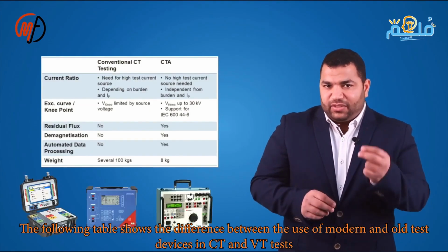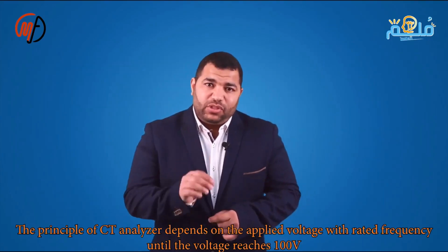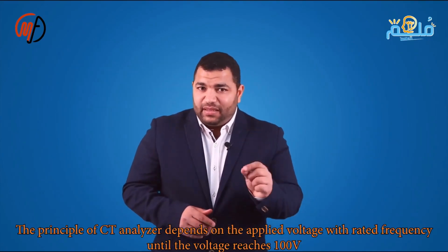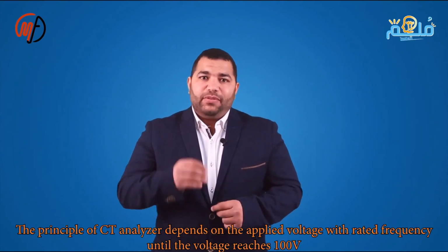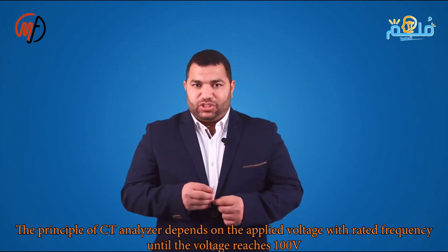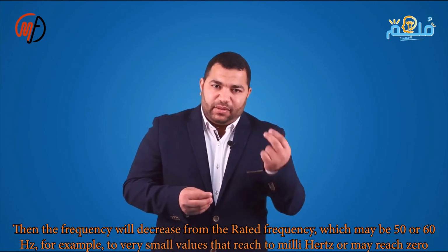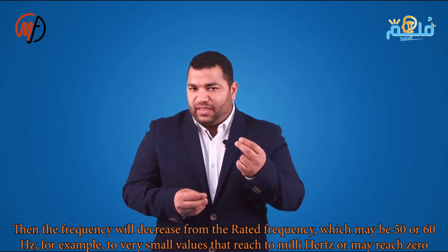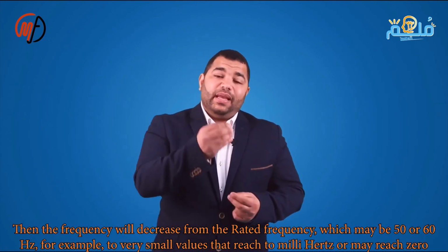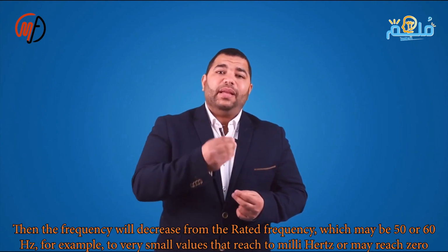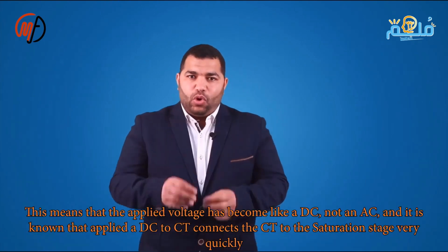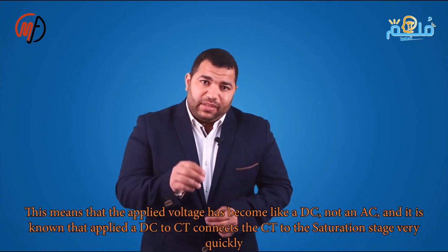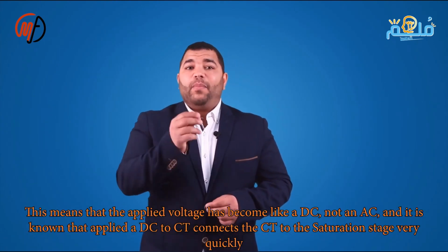The CT analyzer works by applying a rated frequency voltage until 100 V, then gradually reducing frequency from 50 or 60 Hz to millihertz or 0. This means the voltage becomes like DC, quickly driving a CT into saturation. It calculates the knee point, then raises frequency back to rated. The goal is to avoid high voltage for knee point testing, preventing CT winding breakdown.